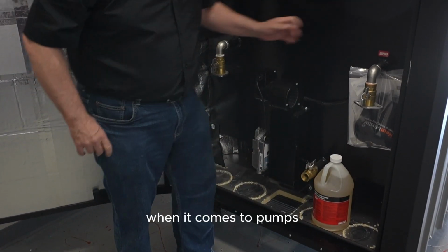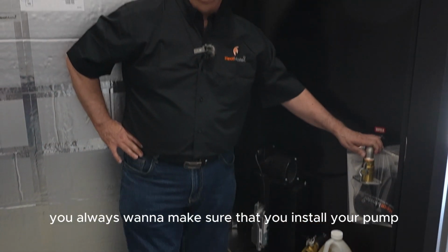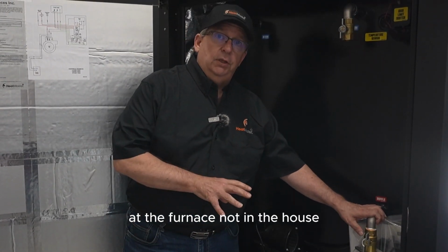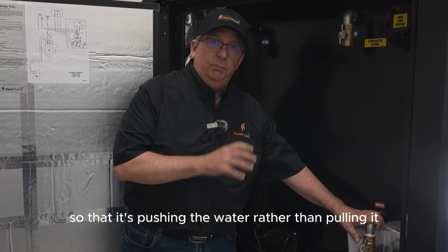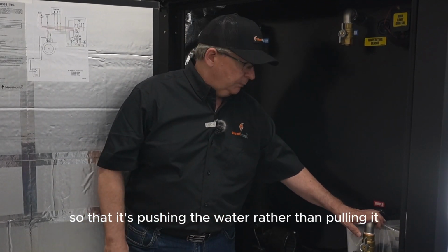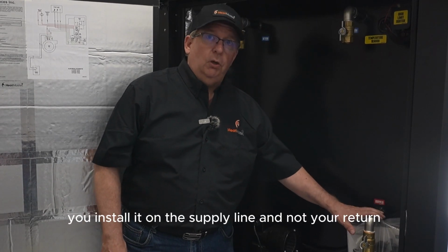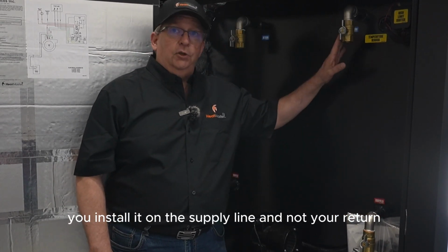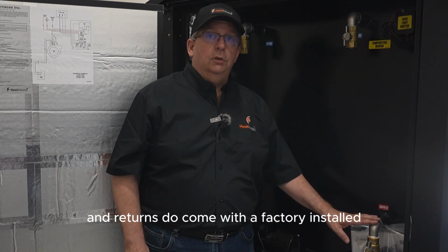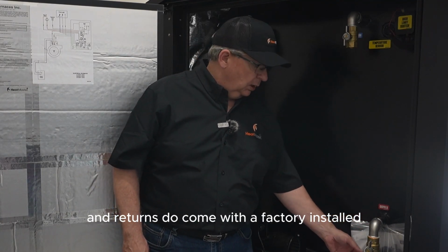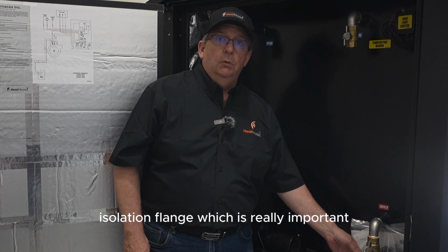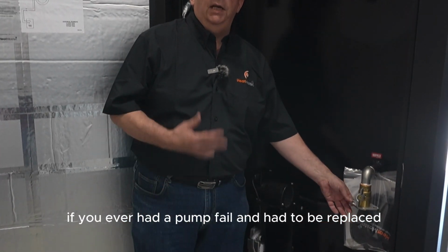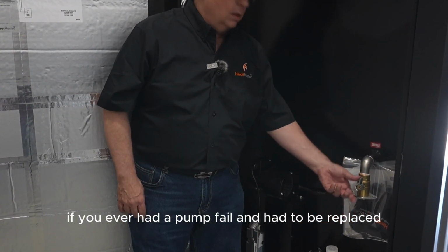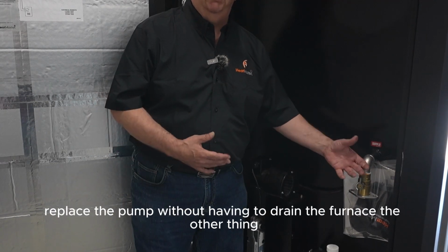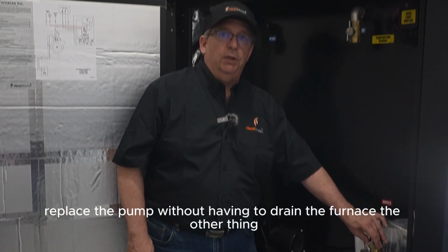When it comes to pumps, you always want to make sure that you install your pump at the furnace, not in the house, so that it's pushing the water rather than pulling it. And you want to make sure you install it on the supply line and not your return. Now, both your supply and returns do come with a factory installed isolation flange, which is really important. If you ever had a pump fail and had to be replaced, you're able to shut off that water, replace the pump without having to drain the furnace.